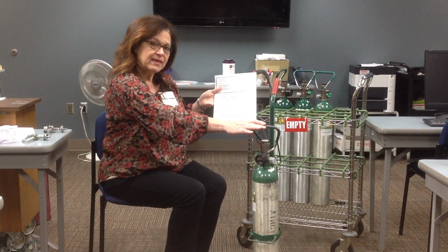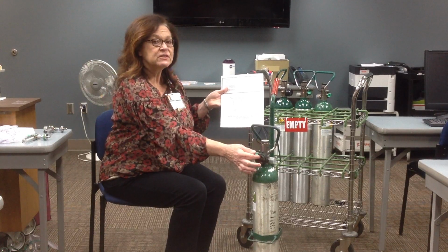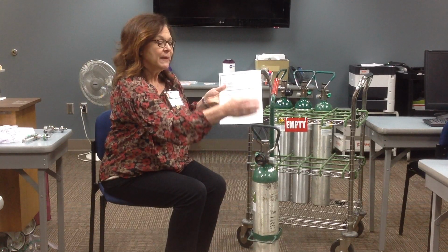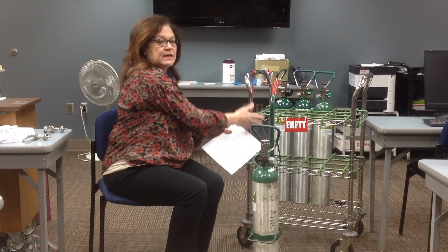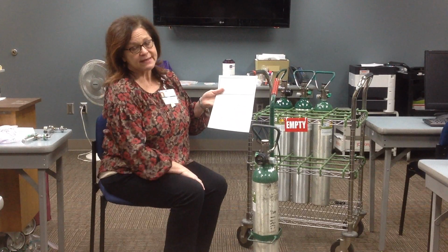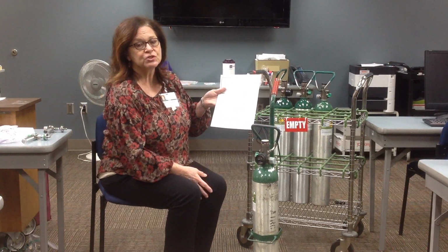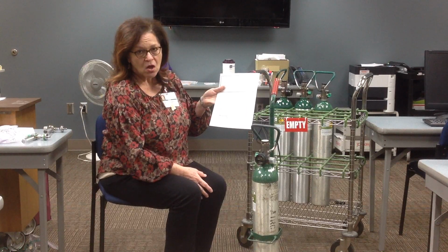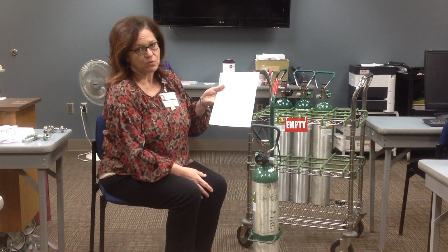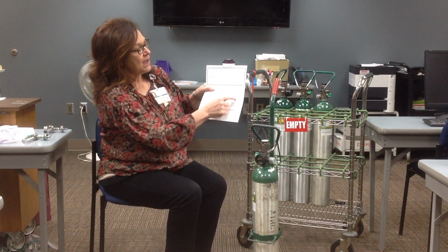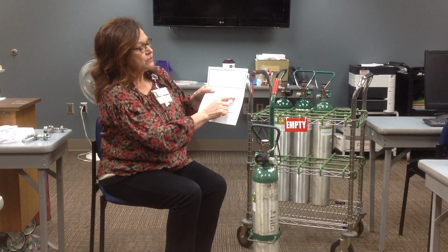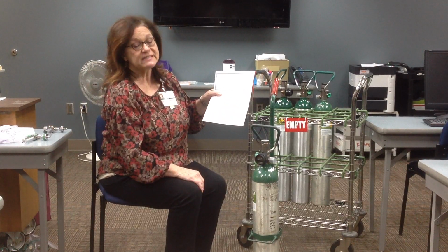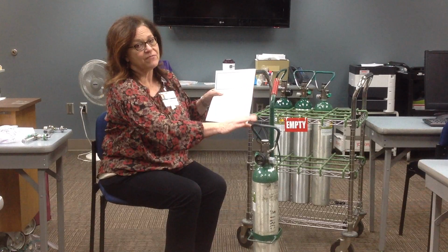What we find that happens is when it gets close to the 500 red zone, people will take the tank and put it in the empty rack. There's still gas in there that we can use, and we encourage you to use them as long as is safely possible. Because if you look over at the 500 chart, a 2 liter a minute nasal cannula would last for 70 minutes on that tank at 500.